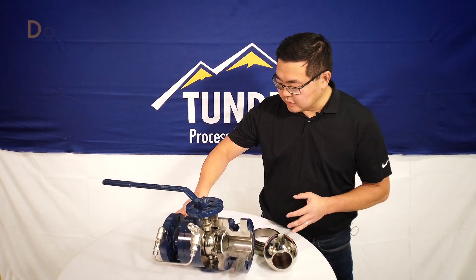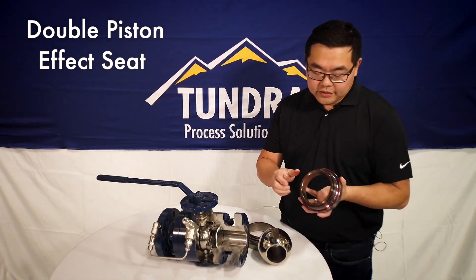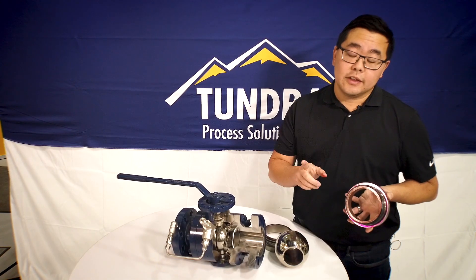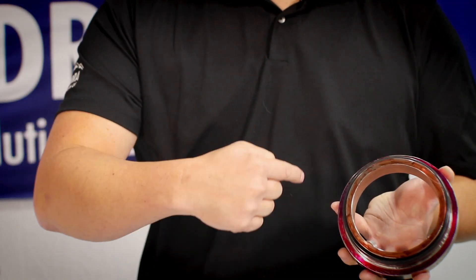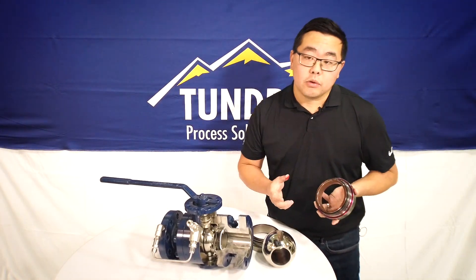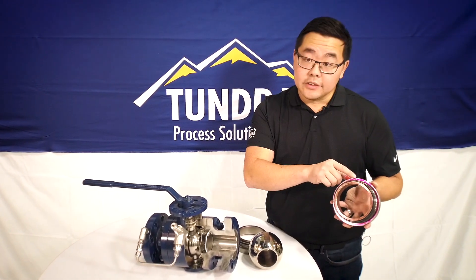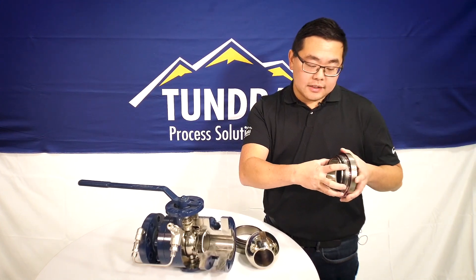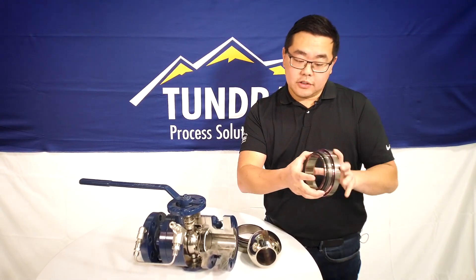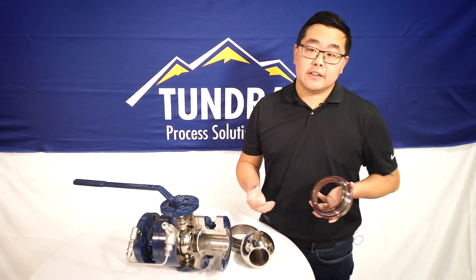The other type is called a double piston effect seat. Similar to the single piston effect seat, your process pressure acts on this brown seat ring. However, it has another piston effect seat shown here in purple, and your internal cavity pressure actually acts on that one. This is important because if you have liquids trapped inside the center cavity, they will act on this purple face, and during something like liquid thermal expansion, that process fluid will push the seat carrier harder into the ball to create a tighter seal.